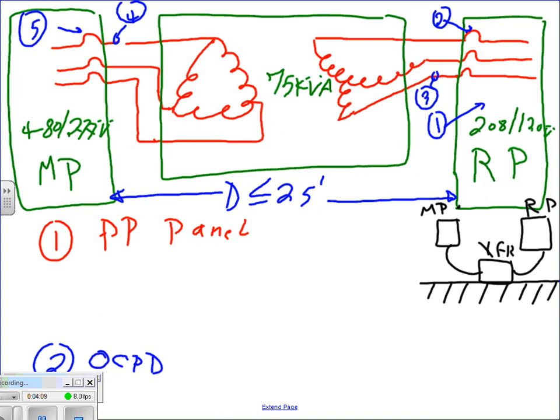Why 25 feet? The code allows you to do certain things within 25 feet that you cannot do otherwise. If this setup qualifies, all you need is a circuit breaker on the first panel feeding the transformer and a circuit breaker on the second panel - no fuses or circuit breakers anywhere in between. The two circuit breakers sit inside the panels. That's the great thing about the 25-foot rule: the main breakers of the panels serve as your overcurrent protection.